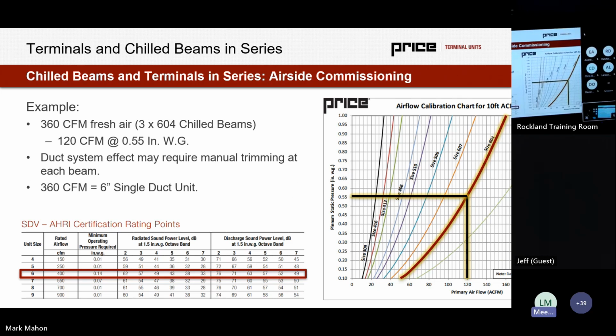So a quick example of this, and once again, pretty technical, my apologies, but let's say we have 360 CFM of fresh air required for a zone. Well, in this case, the way I've broken this out is 120 CFM through 3 individual 10-foot 604 size chilled beams. And that would result for 120 CFM for that beam type, we're needing 0.55 inches of static pressure in the backpan of the beam. And that's kind of ideal for that 0.4 to 0.6 range, which we're ideally targeting for design day.